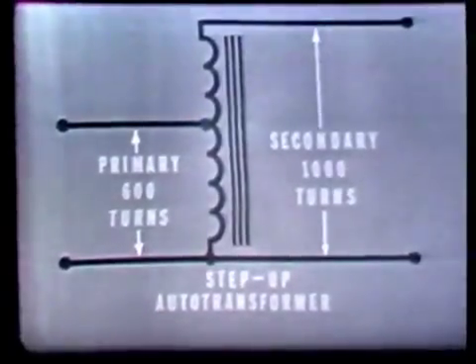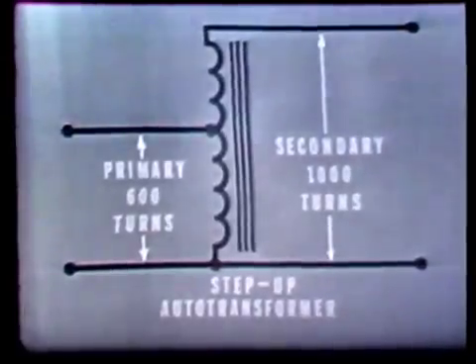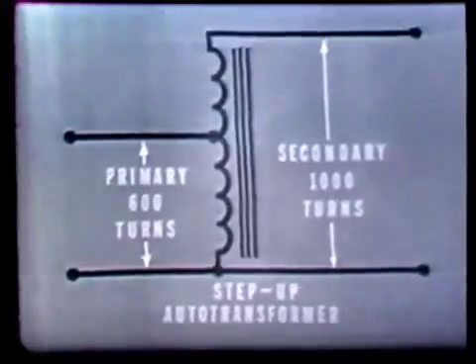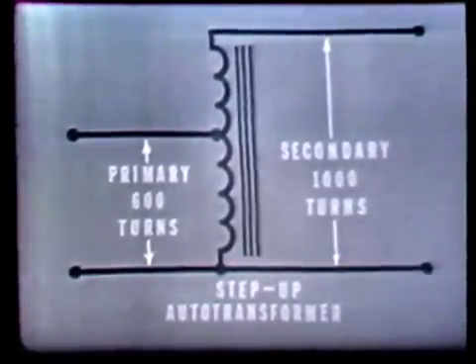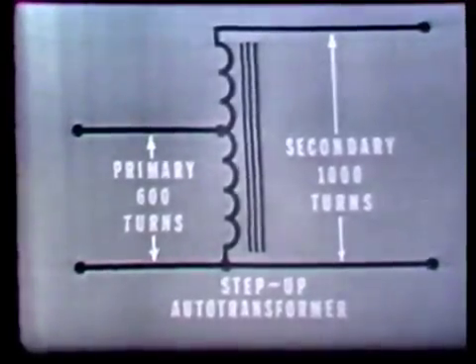A special type of transformer which uses only one winding for both the primary and the secondary coils is the auto transformer. An auto transformer can be used either as a step-up or as a step-down transformer. When used as a step-up transformer, all of the primary winding is part of the secondary winding. Here you see that the winding has a total of 1,000 turns — 600 of these turns serve as the primary while the entire 1,000 turns serve as the secondary.